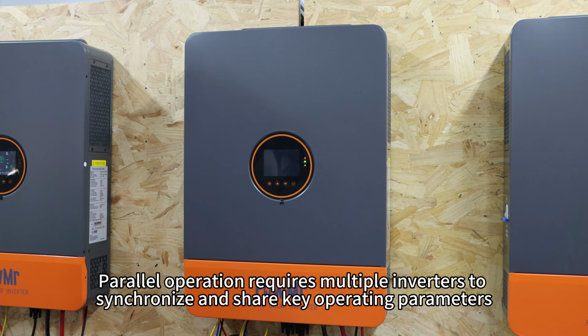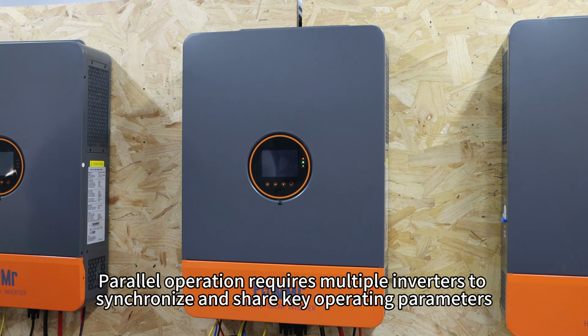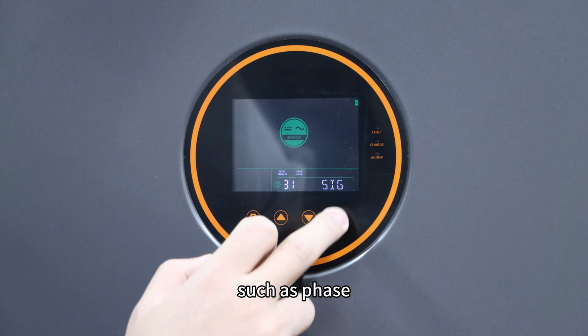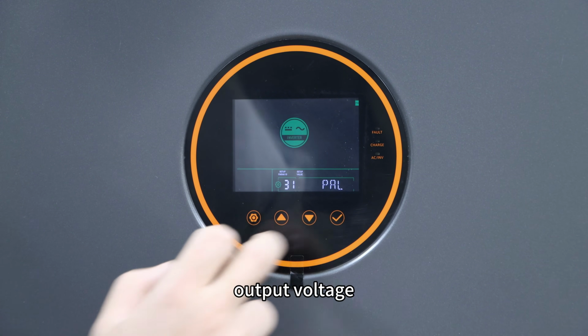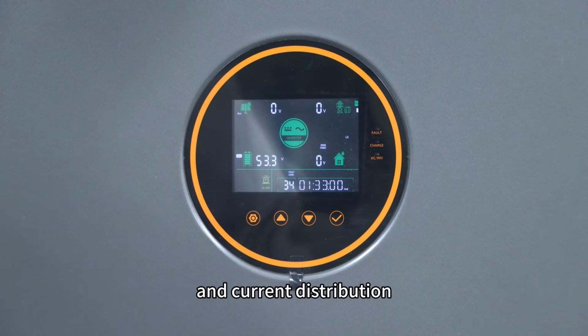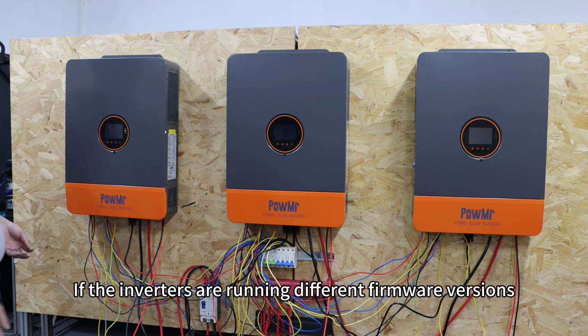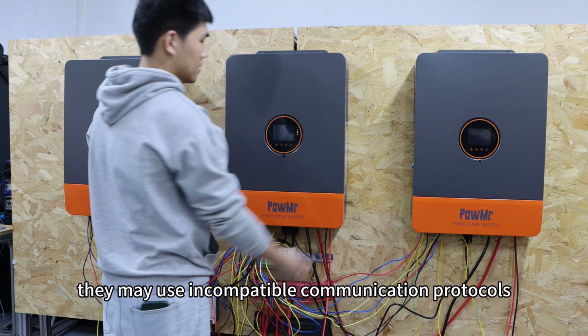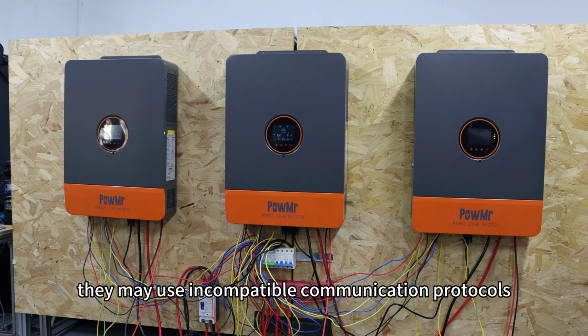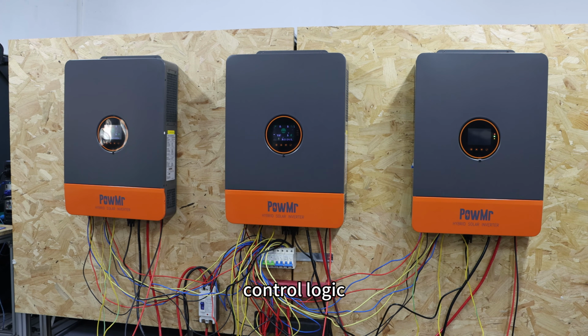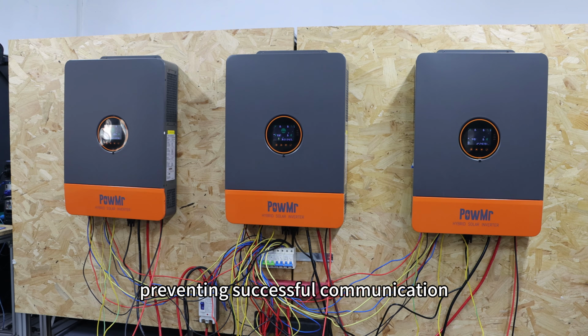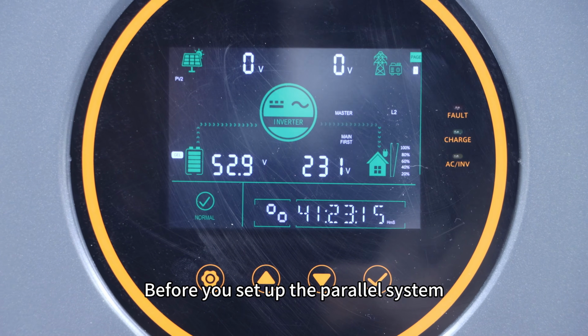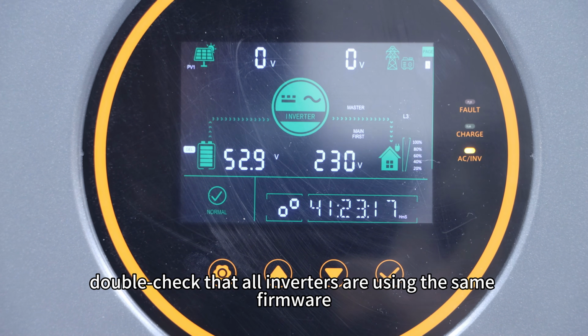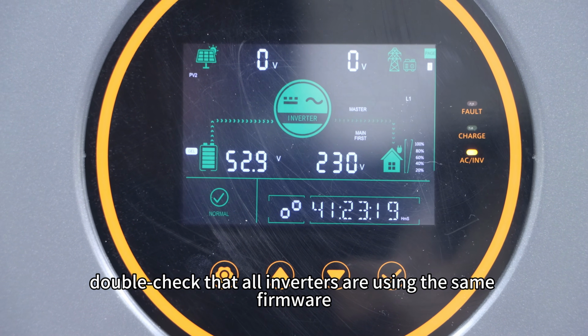Parallel operation requires multiple inverters to synchronize and share key operating parameters such as phase, output voltage, and current distribution. If the inverters are running different firmware versions, they may use incompatible communication protocols, control logic, or internal functions, preventing successful communication. Before you set up the parallel system, double check that all inverters are using the same firmware.